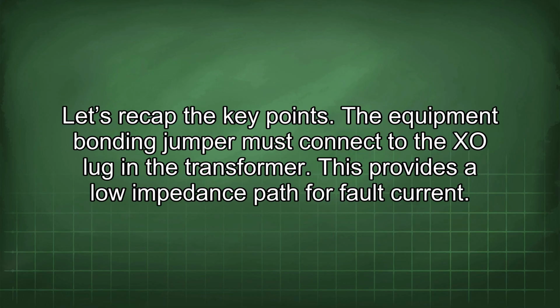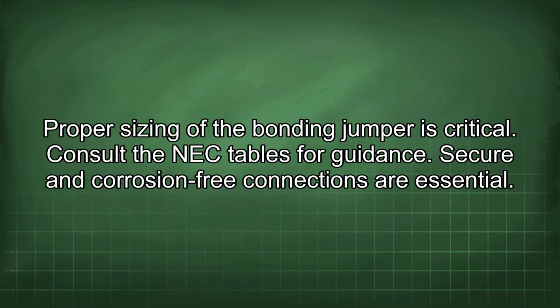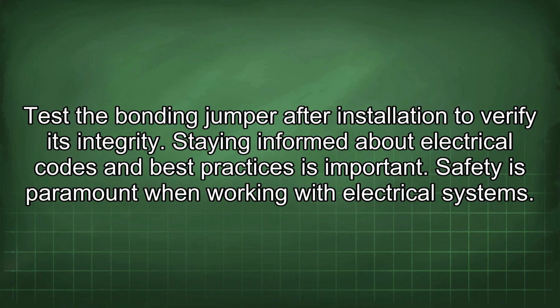Let's recap the key points. The equipment bonding jumper must connect to the XO lug in the transformer. This provides a low impedance path for fault current. Proper sizing of the bonding jumper is critical. Consult the NEC tables for guidance. Secure and corrosion-free connections are essential. Test the bonding jumper after installation to verify its integrity. Staying informed about electrical codes and best practices is important. Safety is paramount when working with electrical systems.